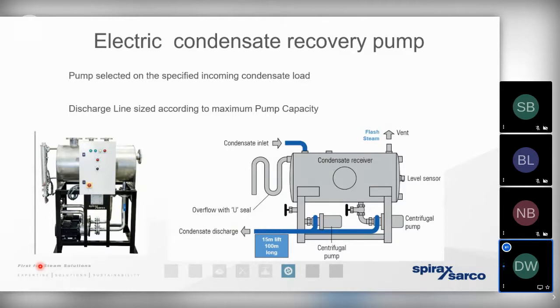Now, a common problem that we also encounter with condensate recovery pumps is, well, imagine if we've got very, very wet steam being delivered to a heat exchanger, and therefore we're condensing more and more steam than we expected. Well, by nature, we'd have more condensate to recover. It may well be that the original condensate receiver is undersized. It may well be that we've added a new heat exchanger into the plant room without giving thought to the additional burden of condensate that the pump would need to encounter.